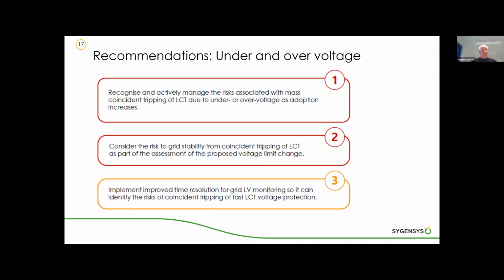We also highlight that the risks to grid stability from coincident tripping need to be considered as part of any changes to voltage limits in the GB grid, and specifically the consideration of a change from the -6% to the -10% limit, but more generally also within things such as the voltage control processes used both at transmission and at distribution level.